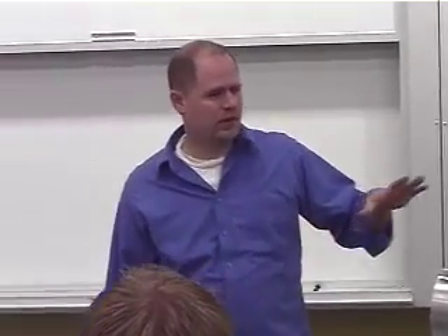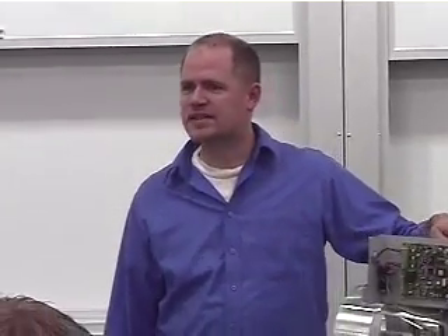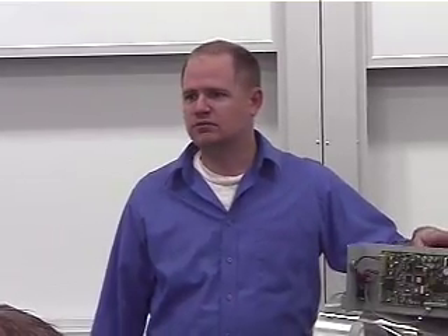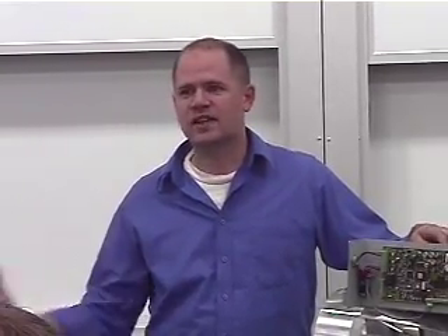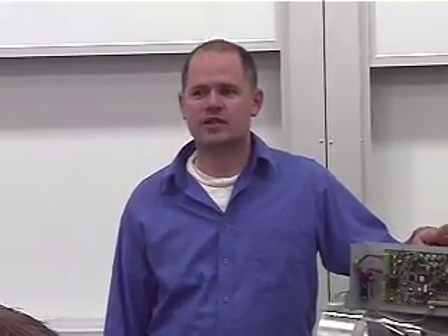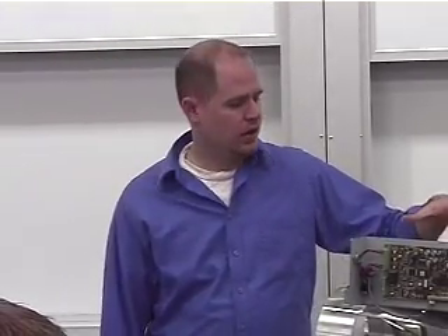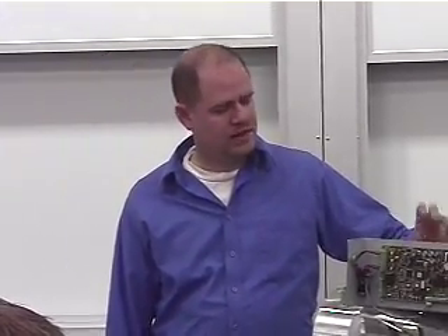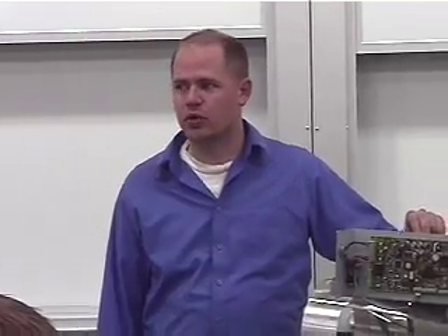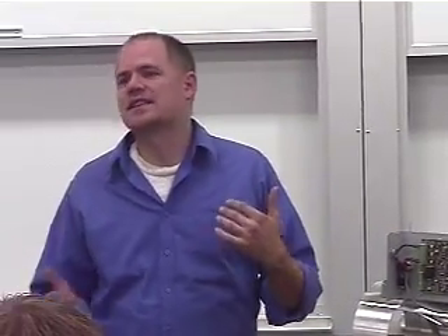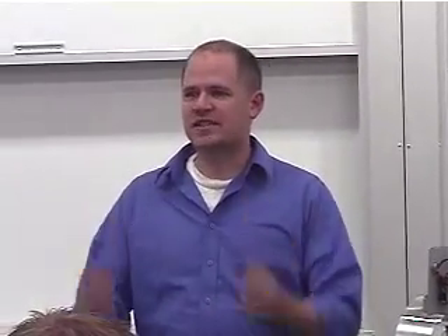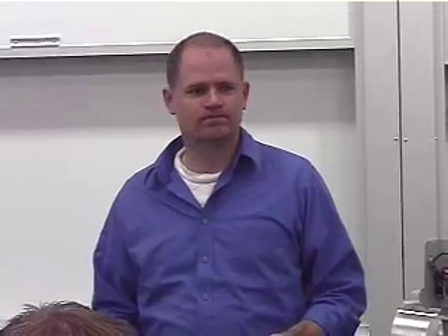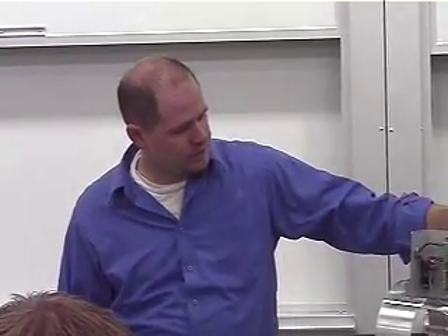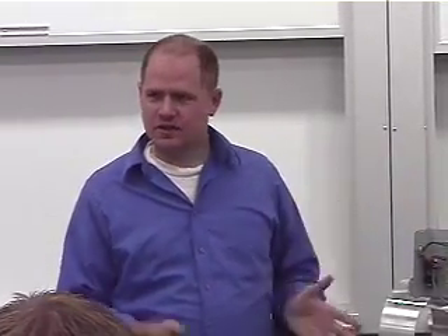They get to, I think it's 90% of the flow within 1 second. And then it's maintained in the room and your offset's maintained. Everything responds very quickly on those. If you see a style with this, it means that there's probably no hoods in the room and they're just maintaining offset control based off temperature. So it doesn't need to respond quickly because nobody's going to come in and slide a sash up and down. So that's the basic description of this.